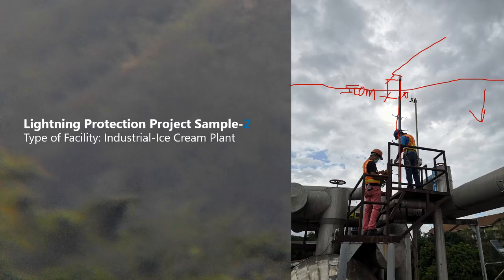If it is installed along the pipe, I think it is best, because the lightning protection system is there before it could strike here. That's my main reason. But again, there is a prevailing code that still allows this, but as a practice, I'm not allowing this kind of installation.